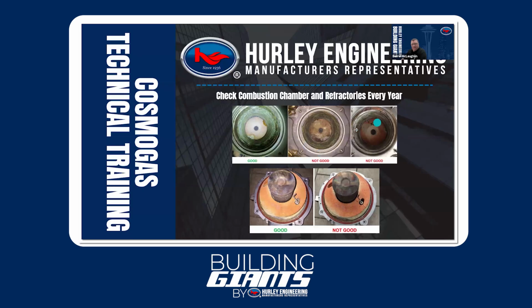That's not good. And the other thing too, if you see in here, there's a crack in that refractory on this far right one. This is a bad example too. Not only that, but your metal retaining washer that holds that refractory on has gone super dark. All these things are indications that you're not in good working order. And if I go down to the burners, same thing. This is going to be in the presence of flame all the time. We don't expect it to look brand new, but we don't want it to look burnt or crispy or have cracks in the refractory, like right here by this flame rod, if you can see that. So just some good ideas of where we can be, like this. We just don't want to be here.